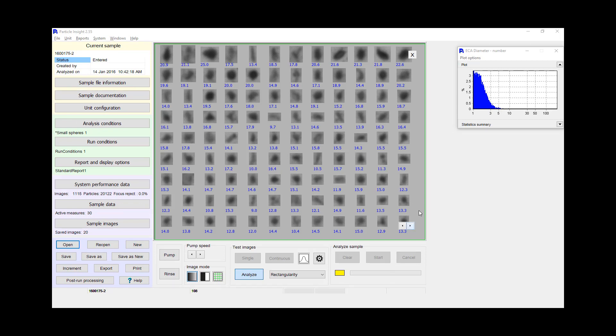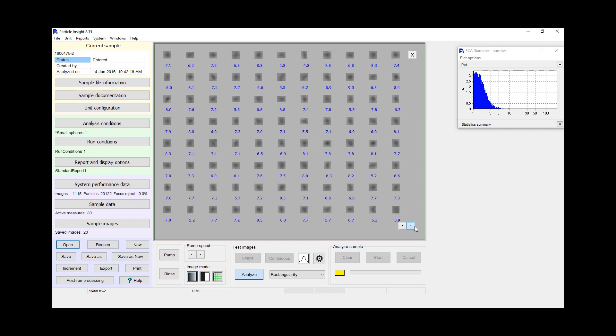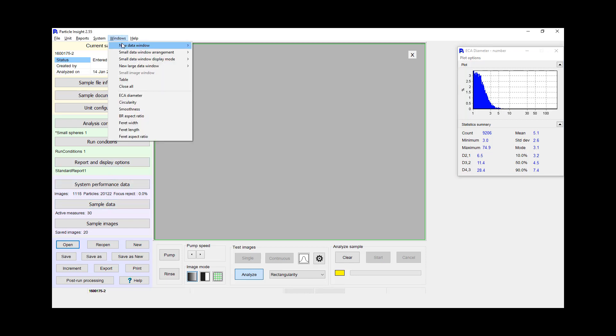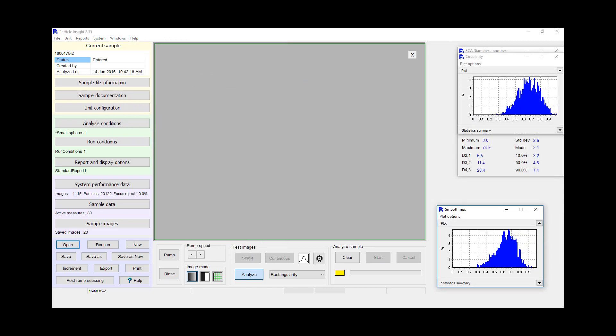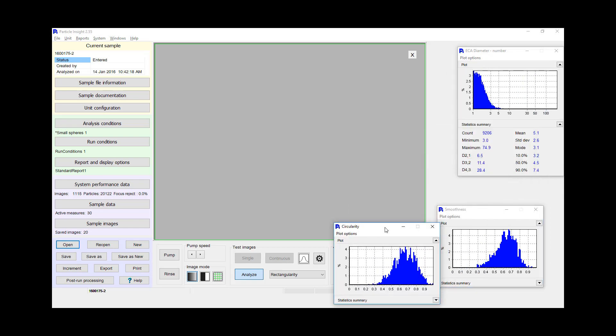So here on a number-weighted distribution showing all 20,000 particles, we can see that they are definitely irregular in nature. It'll be interesting to see what the average circularity is. Let's open some of these measurements — the mean size by number-weighted distribution is about five microns and the mode is about three microns. I can look at all the individual sample measurements one at a time — I could look at circularity and smoothness, and I can see they're not very smooth and not very round.